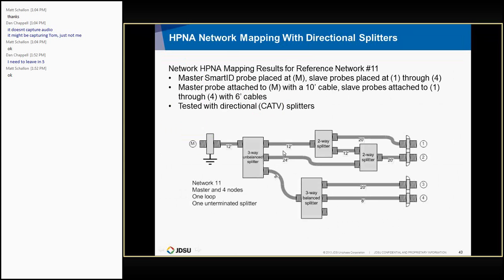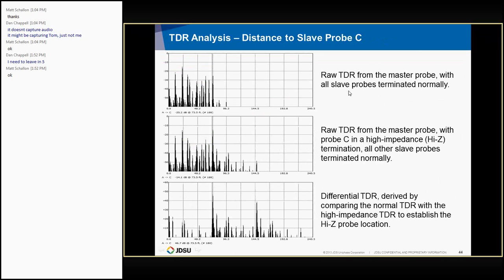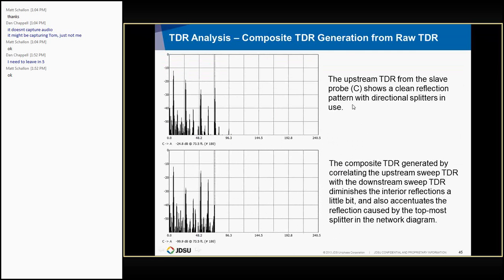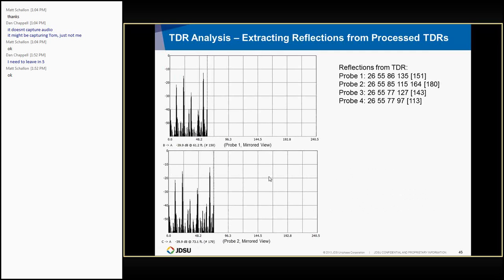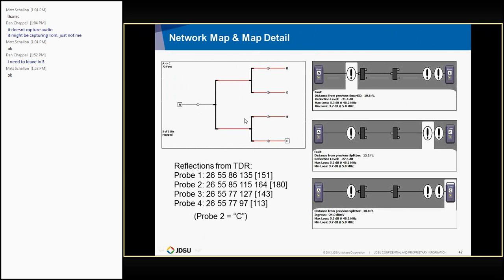Mapping with the directional splitters works pretty good. I show the same basic sequence, pulling out the distance. The distance I've got marked with a cursor here. Then here, this is the composite TDR, and this reflection here is diminished a little bit by the correlation, but it's not diminished excessively. So in this case, because it is directional splitters, this pattern is actually clean, and you don't have to take this step, but it doesn't hurt you to do this. In all the testing I've done, the directional splitters, we seem to pick it up pretty good. We don't seem to hurt the mapping with the correlation process. So this shows how the reflections are finally analyzed and grouped into the map. All this red is because these paths fail the loss test across those paths. That's why they're marked in red.